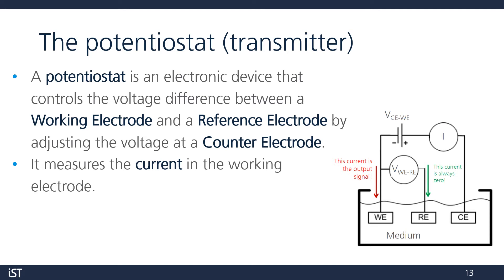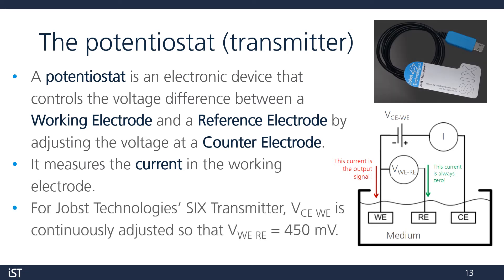But how do we measure this very small current and convert it into an analyte concentration? For this, we use a potentiostat device. This controls the potential difference between a working and reference electrode by adjusting the voltage at a counter electrode. The device measures the current in the working electrode. For the SIX Transmitter from Jobst Technologies, pictured in the corner, the potential across the counter and working electrode is continuously adjusted so our potential at the working and reference electrode is the predefined 450 millivolts.